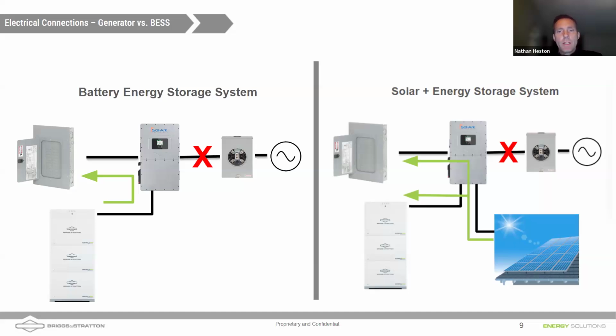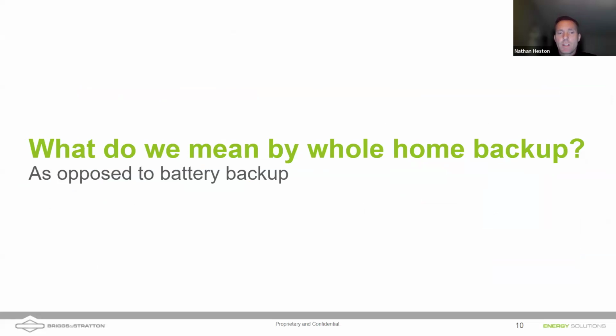And that's the big difference, I think, between a generator-based system, which is there to back up the house. It's either on or off. It's only there to back up the house. Whereas with a battery-based system, you can essentially get it to pay for itself. You can make back the money you've spent on the system by self-consuming energy that you can produce with photovoltaics, with solar panels, with renewable energy sources. You can also do other things like buy electricity cheaply at nighttime and then discharge that battery during the day, doing something like grid arbitrage, as we call it. And if you have peak demand charges at certain times during the day, you can use time of use settings on the inverter to discharge those batteries when electricity is expensive.